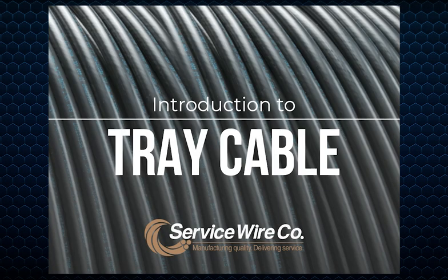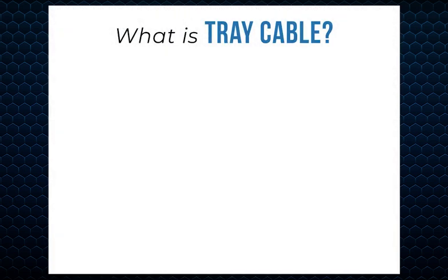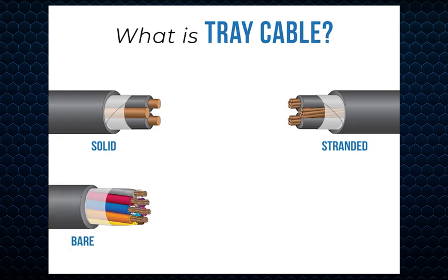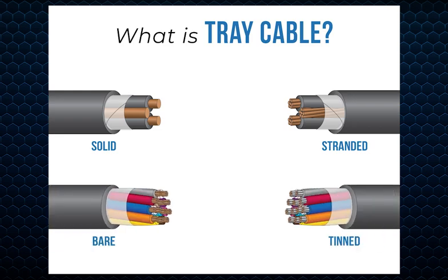Tray cable is a factory assembly of two or more insulated conductors, with or without associated bare or covered grounding, optional fillers, and binding tape under a non-metallic sheath for installation in cable tray, raceways, or where supported by messenger wire. Tray cable is manufactured in accordance to the UL 1277 listing. All service wire tray cable is manufactured using XLPE insulated solid or stranded bare or tin coated copper conductors.